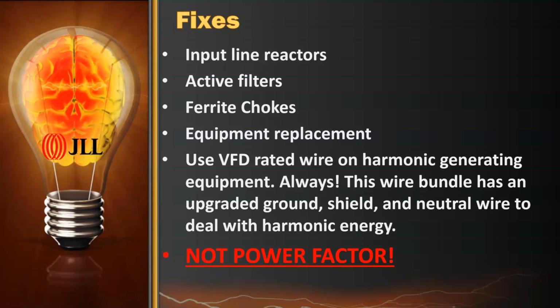On a regular 60 hertz signal that does not have harmonics, the way the electrical code is written and the way the wire is sized, the insulation on the wire and the conduit are enough to deal with the magnetic force generated by that conductor. So if you put the choke even around the wire, you're really not going to affect the 60-Hz waveform. You might slow it down by a fraction of a percent, but the spec for the insulation and the spec for the wire are such that the EM energy is just not strong enough to get outside and cause a problem. And the choke really won't even affect it at all.